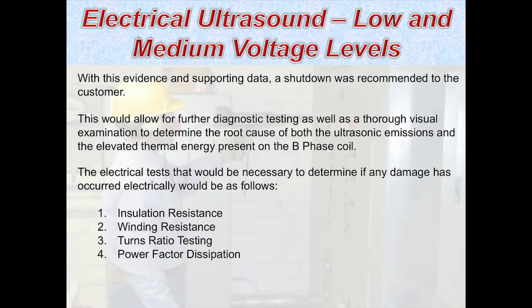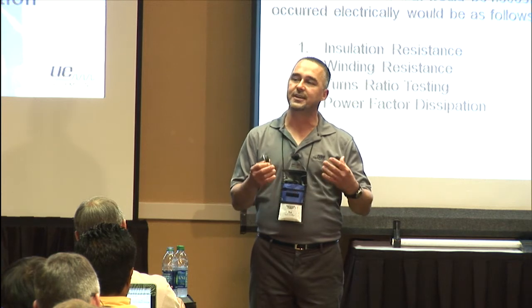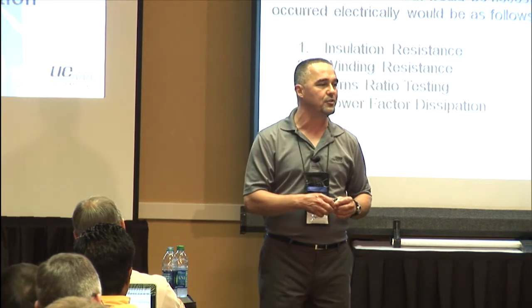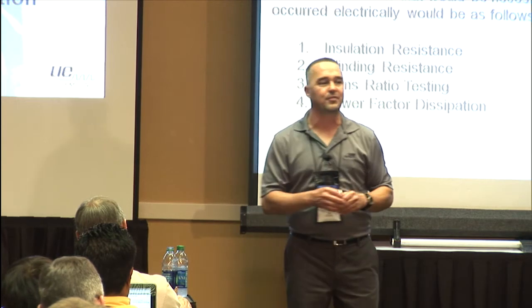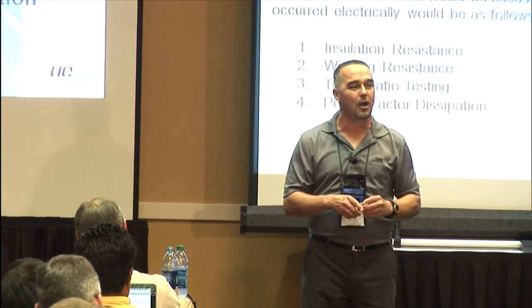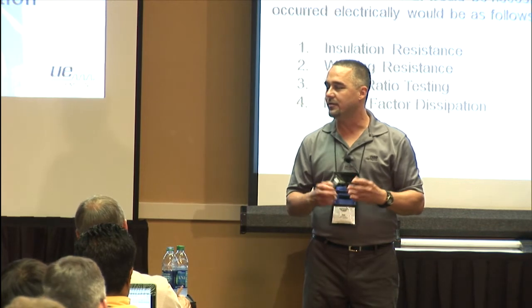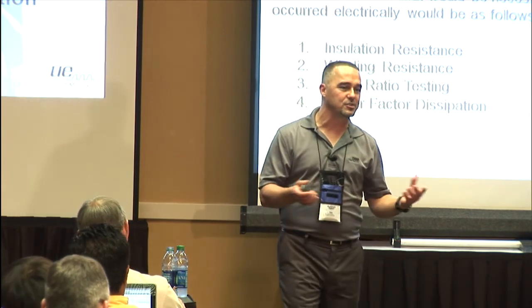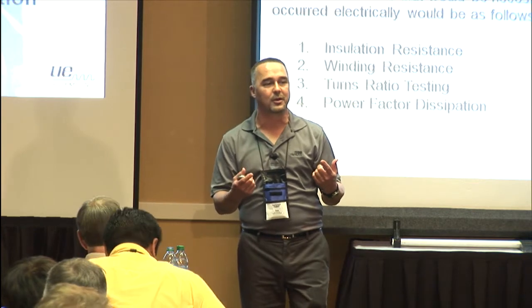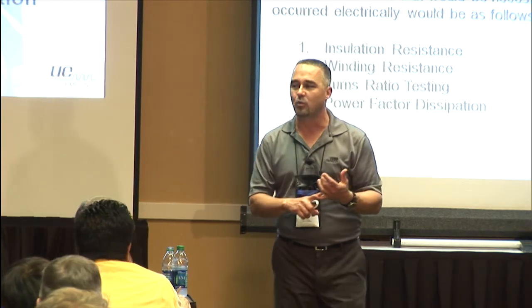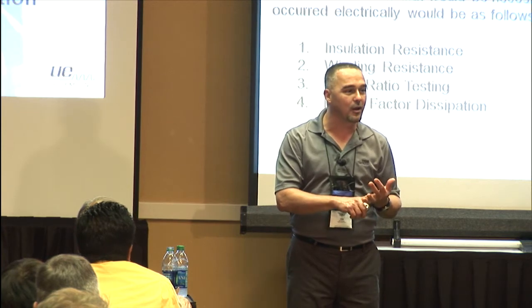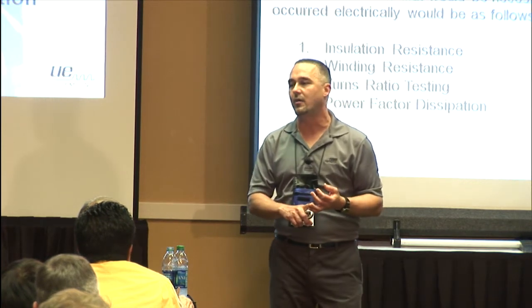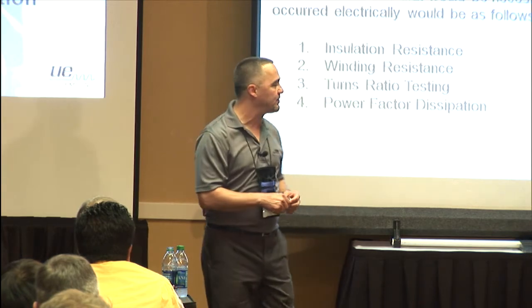Those of you who are not, the insulation resistance testing allows us to determine the health and integrity of the insulating system. You apply a voltage to it, it stresses that material to determine whether or not it can withstand those higher voltages. And particularly with transformers, the inrush currents on them things, when you bring them back online, are very high. So the dielectric strength of that, not just the conductors, but the winding insulation itself better be good. Heating effects will break that down. Something vibrating on it and chafing it will break that material down. This test is a very good indicator of whether or not that's happening.